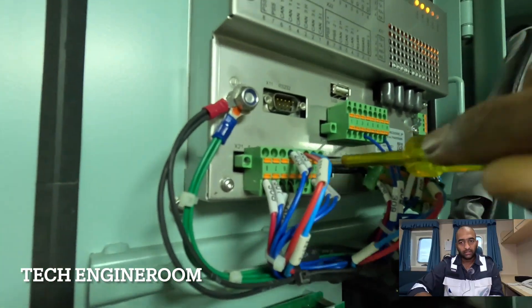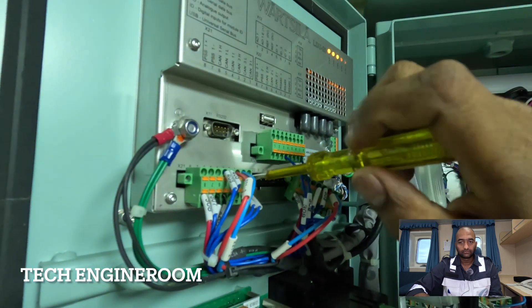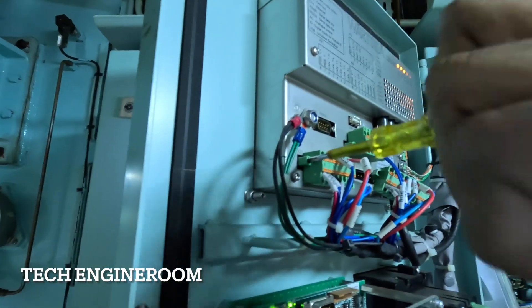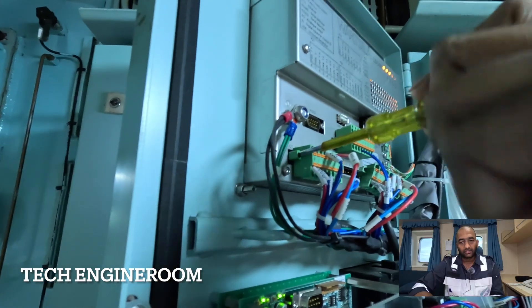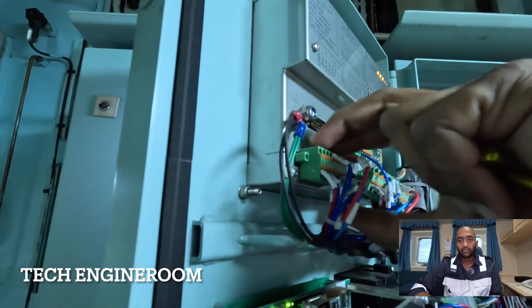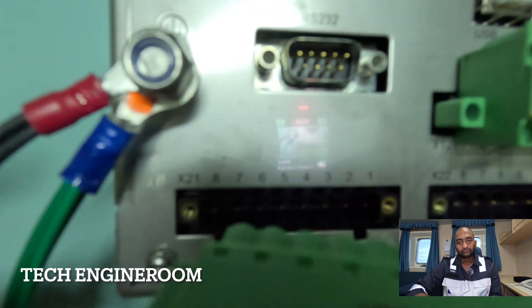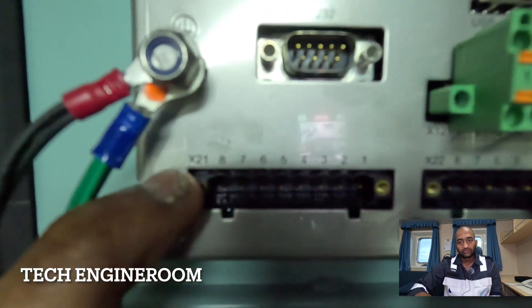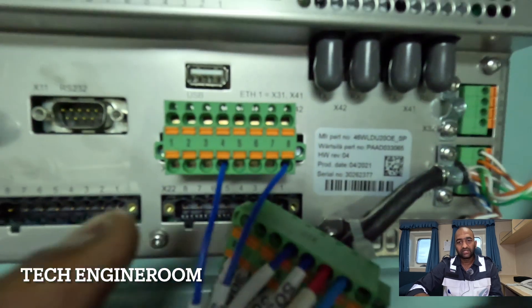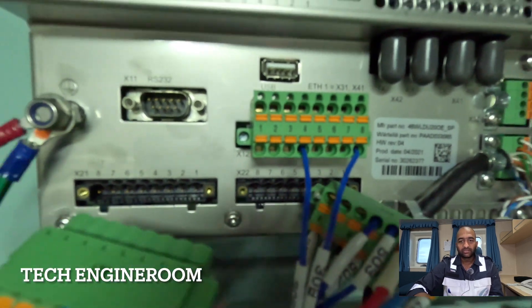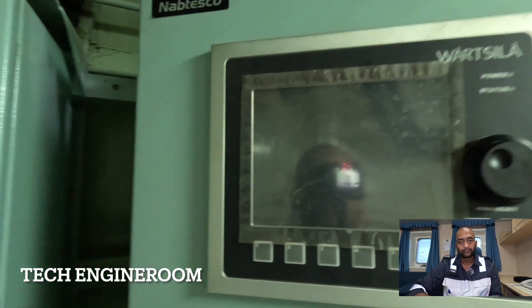Then remove x21. This should be done in order, so don't do it in reverse mode. Once we remove both x22 and x21, the LDU is powered off. You can see this LDU is totally powered off.